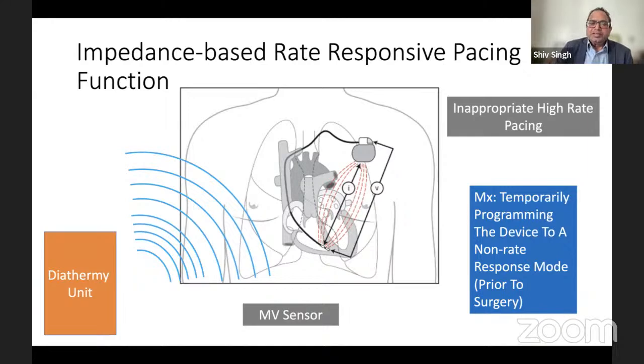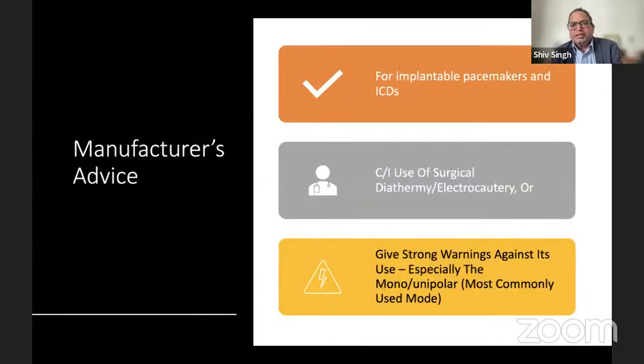Okay. So what do manufacturers advise for implantable pacemakers and ICDs? They say surgical diathermy or electrocautery is contraindicated. They say avoid it as far as possible, and they give a strong warning against its use, especially monopolar, unipolar, which is the most common type used. I mean, they would say don't use diathermy at all if possible. That's what the manufacturer's advice would be for these units.